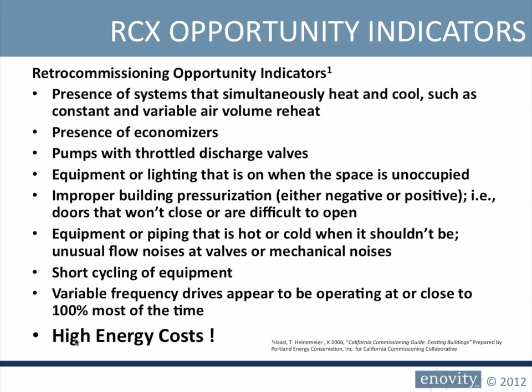High energy costs, and there's kind of two things. You need to have a benchmark for your energy costs, so you know for your type of building and schedule how you're doing, and it's good to do benchmarking against something like Energy Star. Another thing to look at, if you have access to interval data, which is pretty common here in California through a lot of the utilities, is this: if you see high costs through the evening, through the hours that buildings aren't occupied, that's an indicator that you have things on when they don't need to be. Next slide, please.